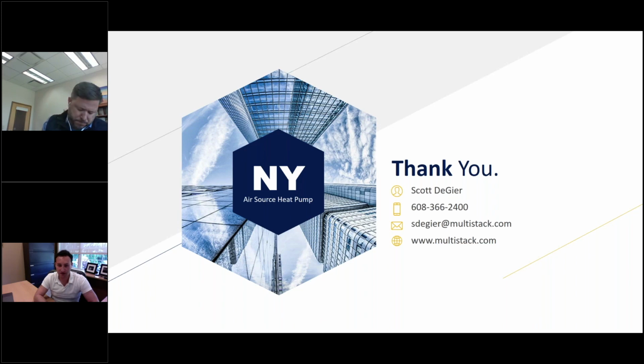Okay. All right, Scott, what refrigerants are you recommending for use in an air to water heat pump? So today, I would say predominantly most air to water heat pumps that are available on the market are using 410A. With an eye to the future, as things are changing, I think there's a roadmap from major compressor providers and major air source heat pump manufacturers to be going to next gen refrigerants. So on that path, if you're talking about a scroll-based product, your path today is 410A for now, which for the life of the equipment will be available, no problems there, and then transitioning into the next gen refrigerants.